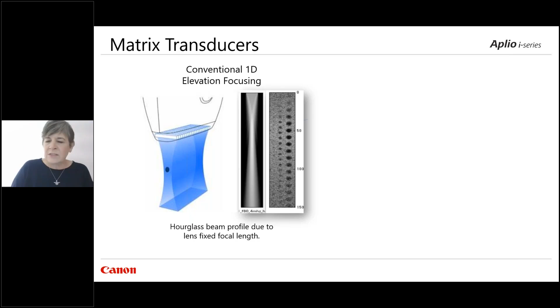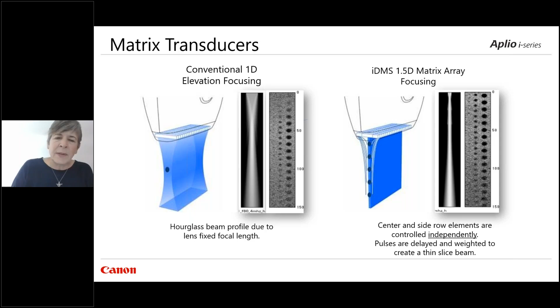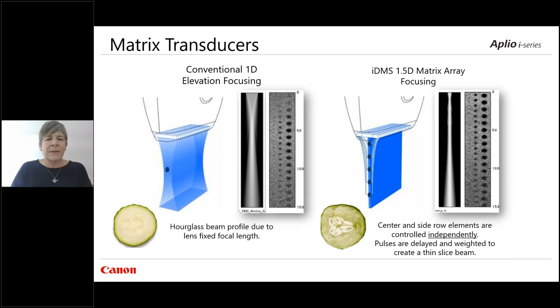We have the ability with each element of the transducer to control how we send that signal in. So we can delay it and get a very thin beam profile from the near field to the far field. If you're looking at the skin surface or even deep against the pectoralis muscle, you're going to see things a lot sharper, with a much thinner beam slice. We know the thinner the slice, the better the resolution.